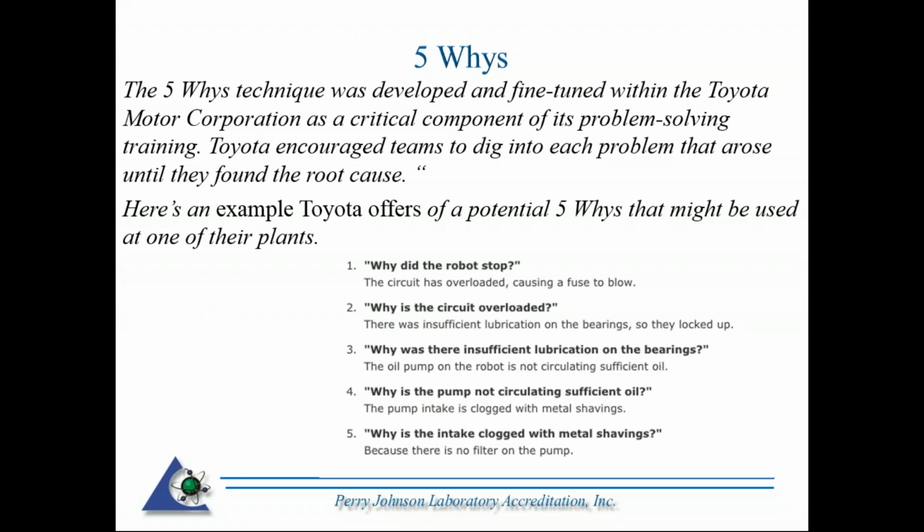Hence, we stopped here; asking why any further is not going to provide any meaningful results. So instead of stopping at the first one, where we simply change the fuse, we utilized the 5 whys, as Toyota did, and came up with putting a filter in to prevent this situation from happening again and causing this robot to stop functioning.